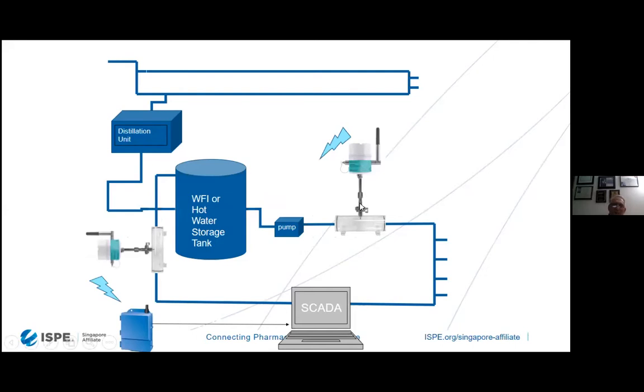Well, primarily the unit is installed directly down from the pump. Why? The pump, because of its cavitation and high velocity, will erode almost all of the thin film of the chromium oxide layer in a very, very rapid manner. What happens is that the pump itself and right here after the pump is going to be where there's the most amount of rouge that develops.